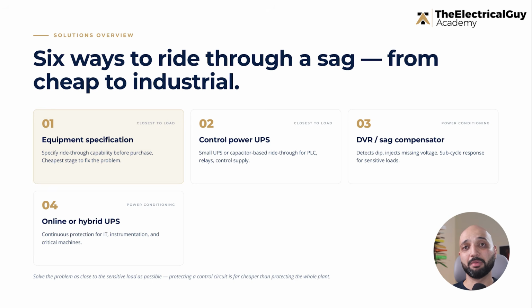A hybrid UPS combines features to provide better regulation and ride-through. UPS systems are excellent for IT loads, control systems, instrumentation, and selected critical machines. But using a UPS for very large industrial loads can become expensive.